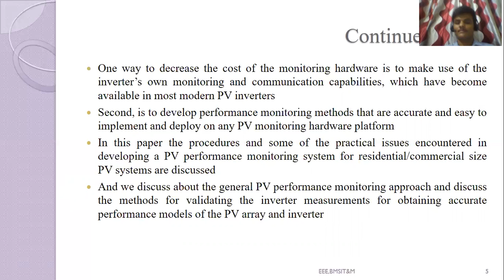Moving on, first we have the development of the performance monitoring system. Here we are developing a performance monitoring system. The operation concept of the performance monitoring system uses a model-based approach to detect the performance degradation of the PV array. The method uses local plane of array incidence irradiance and module temperature using sensors, and it measures that along with the performance model of PV arrays of the inverter.